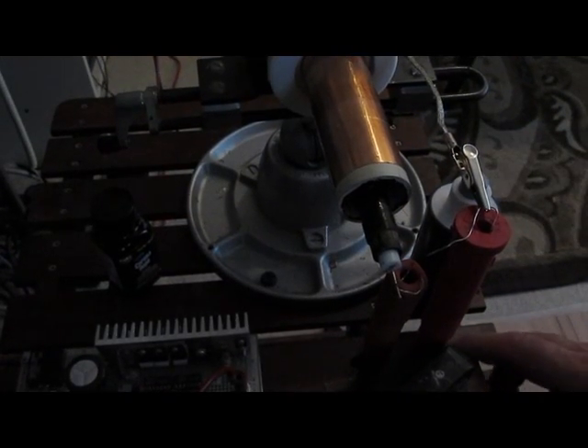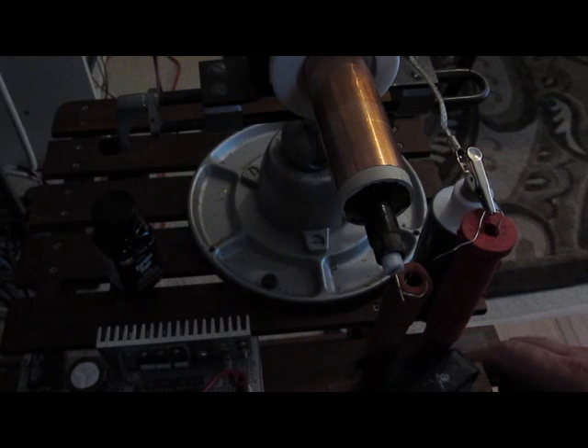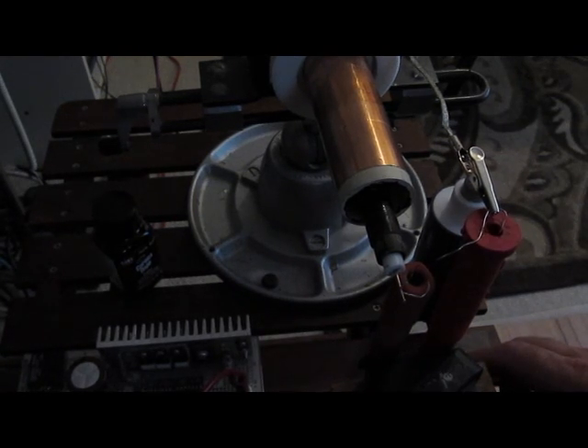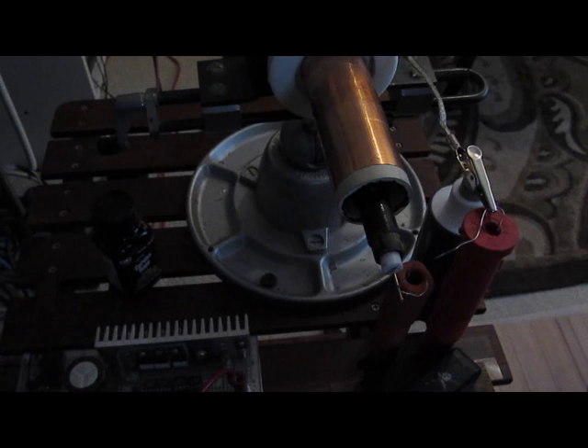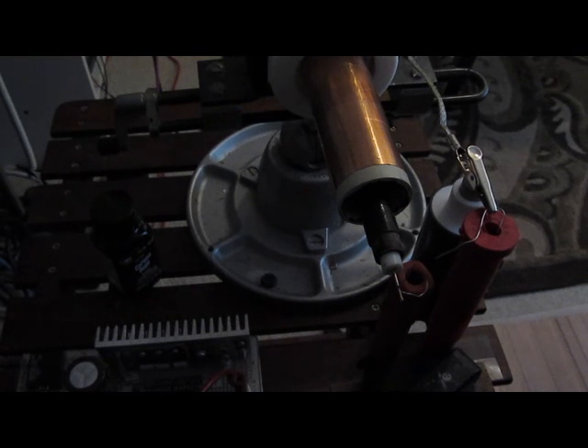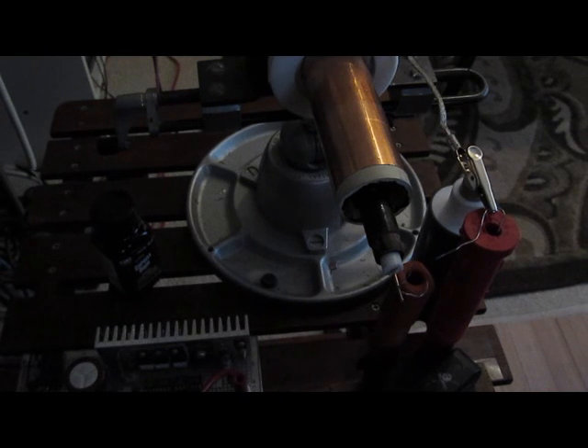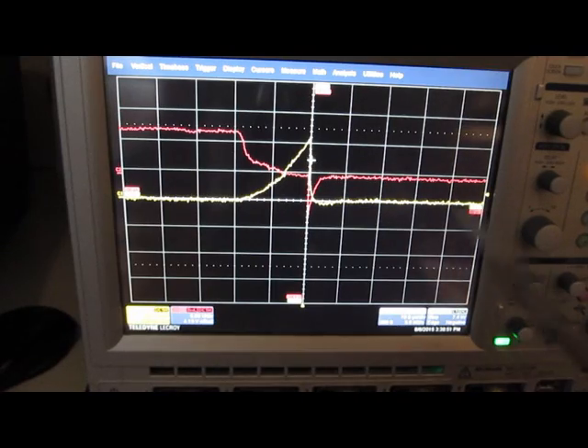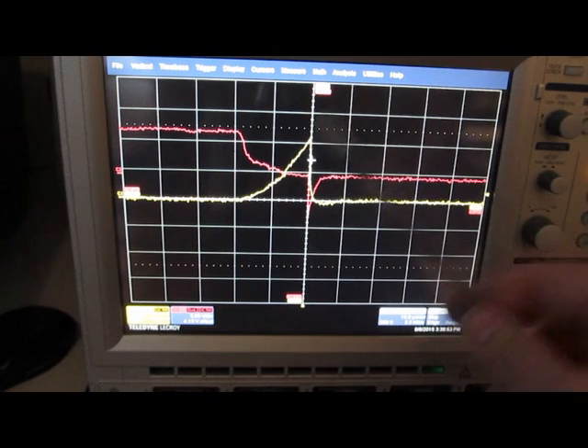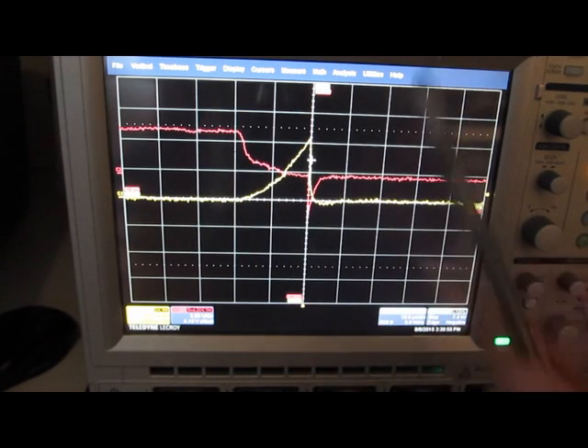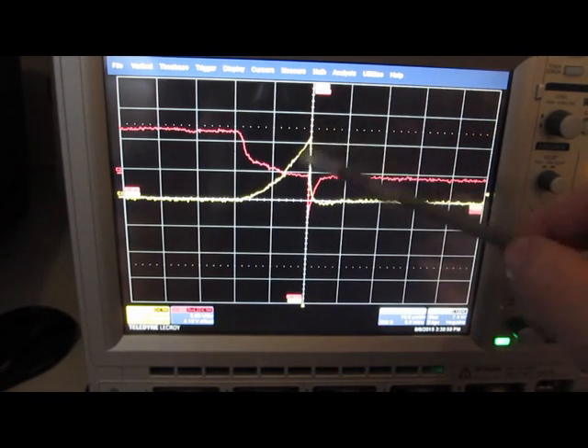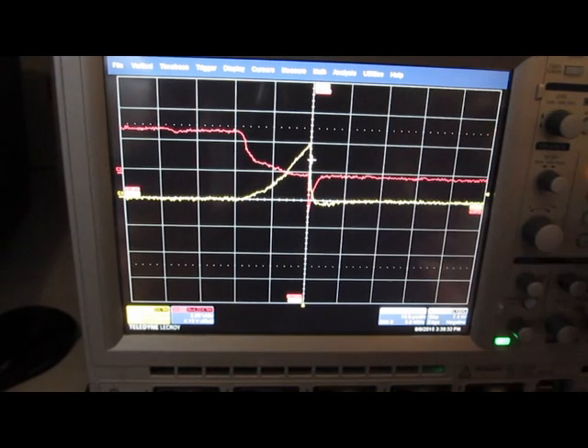Okay, we'll go ahead and increase the gap a little further. And again, I don't see anything inside of the probe. Just visually looking down inside of the end of it here, it looks pretty good. This is looking at 20,000 volts per division here, so we're now about 40,000 volts. So yeah, the waveform looks pretty good.